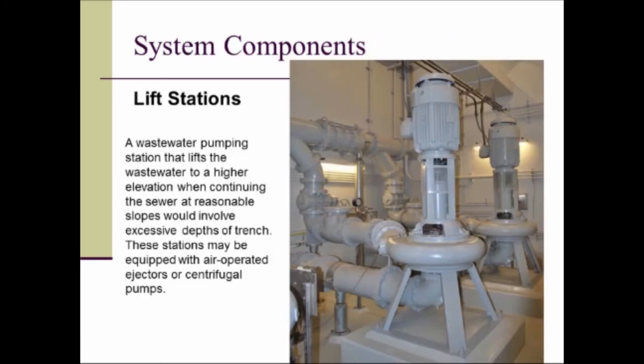The last thing we want to talk about is the lift station. A lift station is a wastewater pumping station that lifts the wastewater to a higher elevation when continuing the sewer at a reasonable slope would involve excessive trench depth. If your trenches start getting too deep to where your manhole access is just too deep down, you'll have a lift station that will raise the level of your sewer and bring the wastewater up so it can continue to drain by gravity.